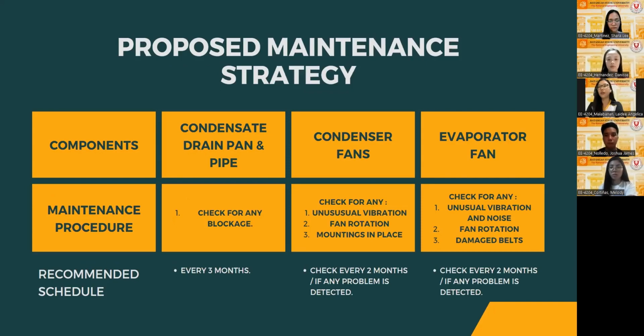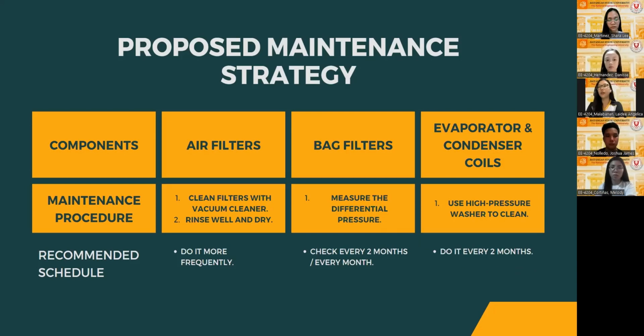This table shows the proposed maintenance strategy that arose in the analysis and evaluation of the problems or issues that occurred in this situation. For the component of air filters, the maintenance procedure includes: clean filters with a vacuum cleaner, tap the filter on a soft surface, then rinse the filter with a detergent and warm water, then rinse well and dry the filters before the reinstallation in the air handling unit. For the recommended schedule, at least every 15 days. If the environment is dusty, do it more frequently.